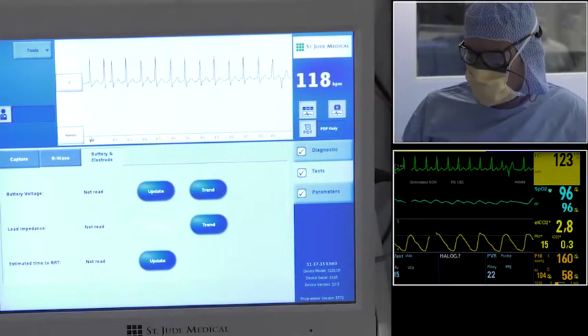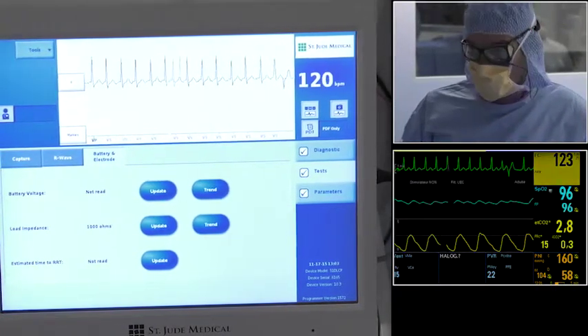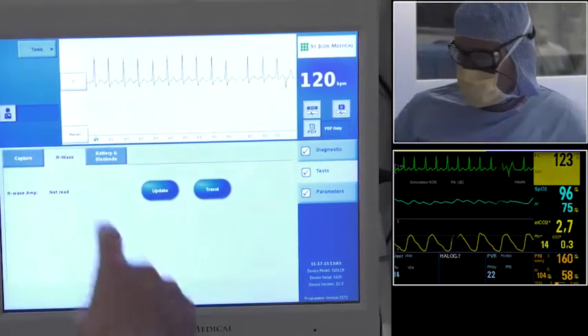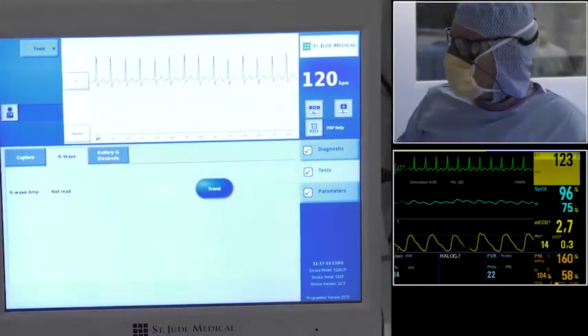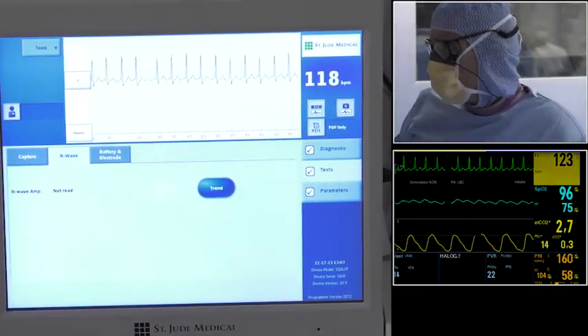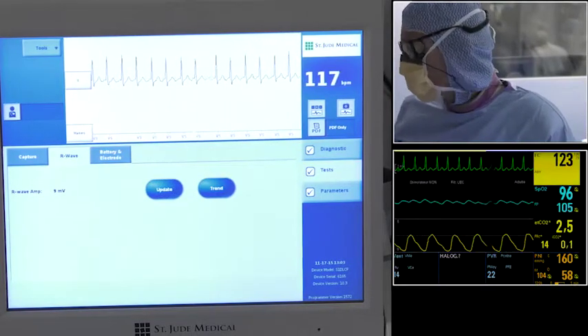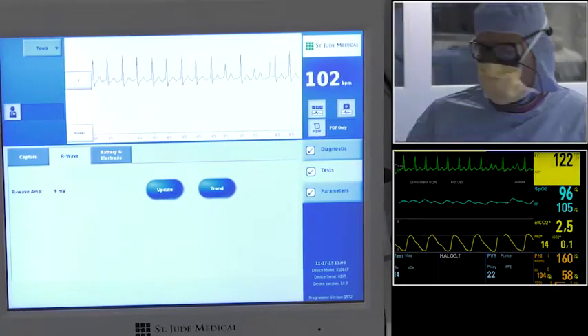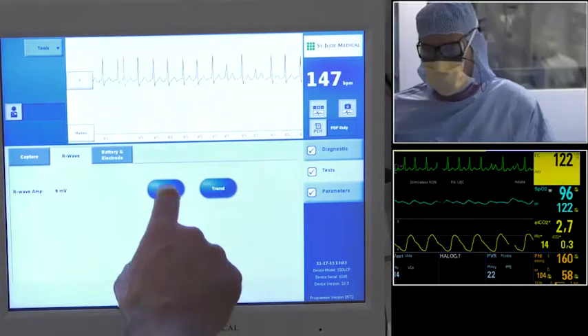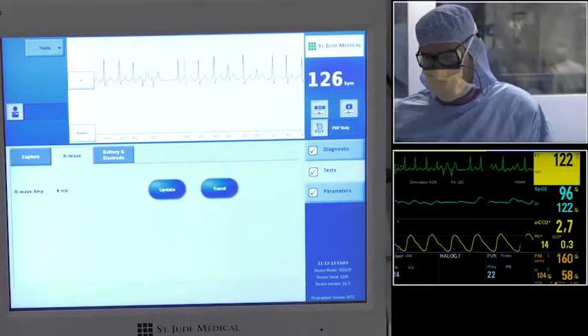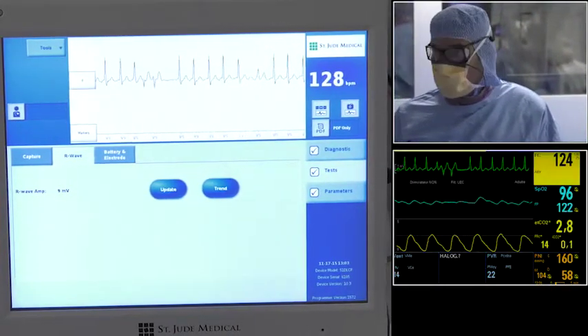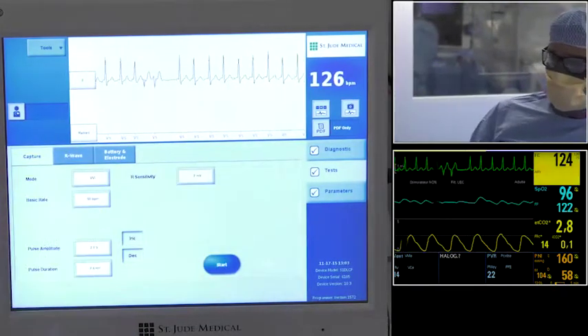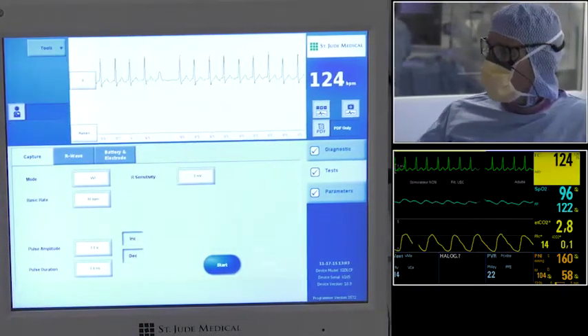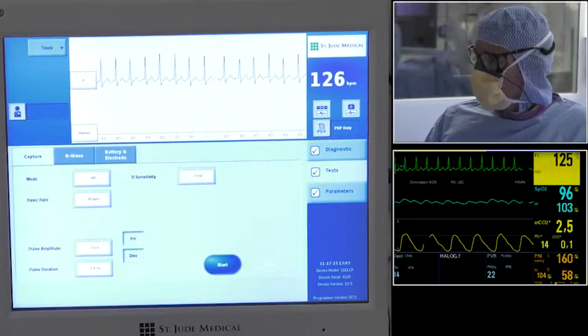So we measure the impedance: 1000. I will check the sensing. What is acceptable, Cedric? Between 200 and 2000. So 1000 is okay, indeed. The sensing is 9 millivolts. 9 millivolts of sensing, very good. So I will do the capture test. We accept up to 3.